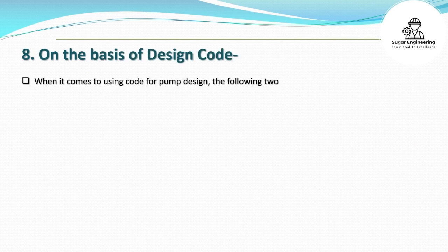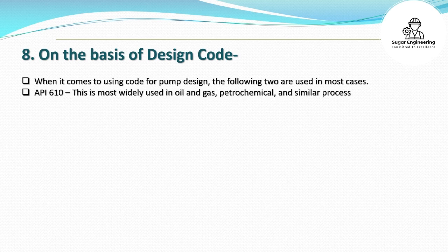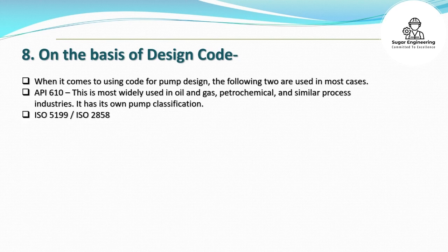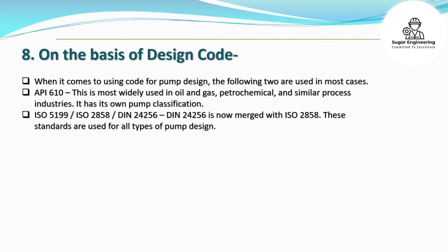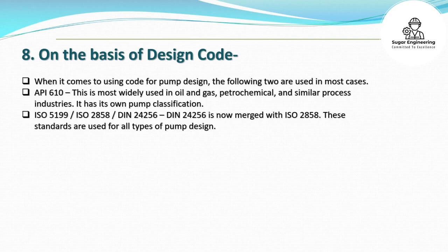On the basis of design code: when it comes to using a code for pump design, the following two are used in most cases. API 610 — this is most widely used in oil and gas, petrochemical, and similar process industries, and has its own pump classification. ISO 5199 / ISO 2858 / DIN 24256 — DIN 24256 is now merged with ISO 2858. These standards are used for all types of pump design.